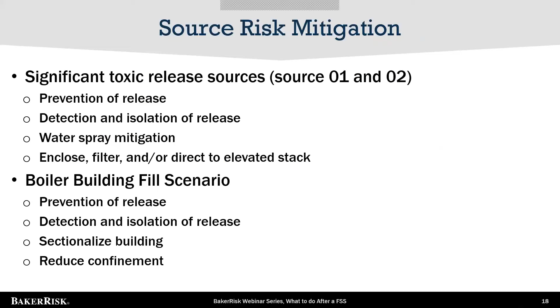Around boiler fill case scenarios, the idea is that you can have an internal release that could fill this building volume and result in an internal vapor cloud explosion. So could we sectionalize the building and make the volume smaller than the entire building volume? Could we constrain it to a single room, for example? Or, an even better option, could we put this boiler outside? Could we reduce confinement around the boiler? Could we open up the walls and the roof? Or if we need a roof, could we at least take out all the walls around the boiler and not have the potential for an internal vapor cloud scenario?